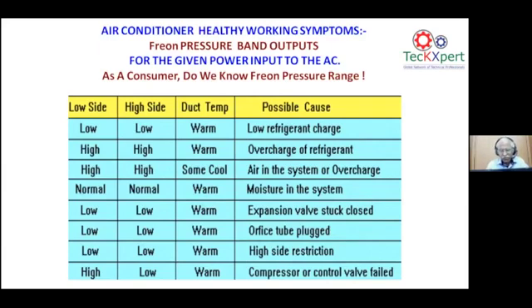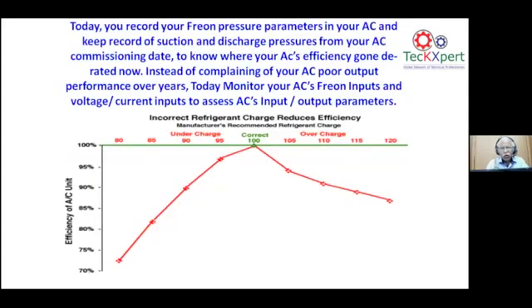Then comes the internals, like the expansion valve or the orifice tube getting choked or plugged. So the charging parameter or the suction parameter is a critical parameter to be monitored in any of your air conditioners, right from a 3 tonner to 100 tonners or more. For higher size tonners, every HVAC OEM as well as the users monitor it. Especially for less than 10 tonners, it is not monitored. Let us monitor it. Normally we have a suction pressure setting of 35 psi to trip and a delivery of 350 psi to trip on an R22.